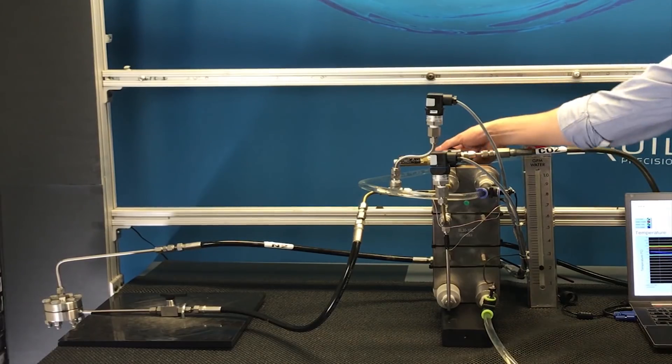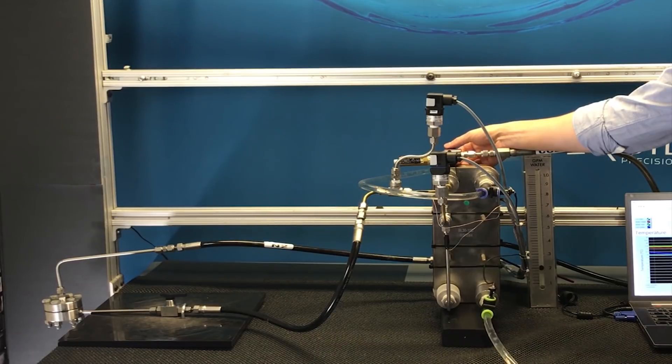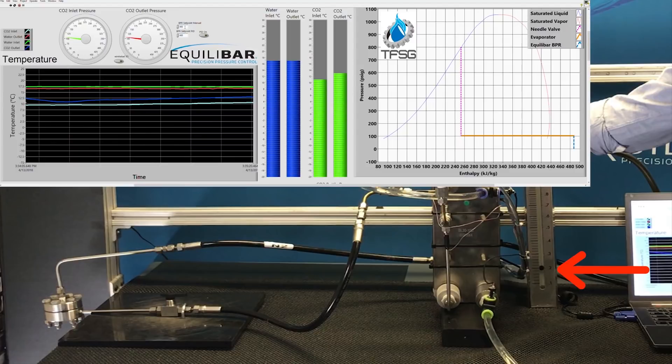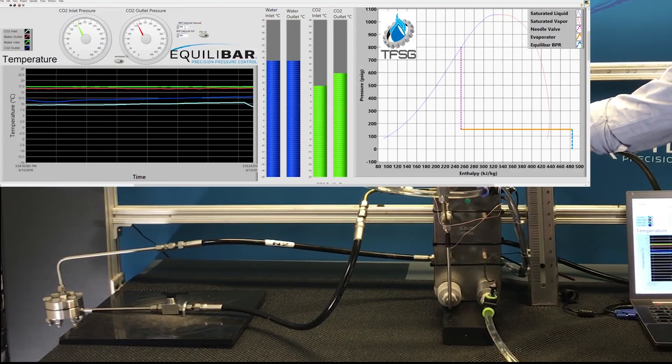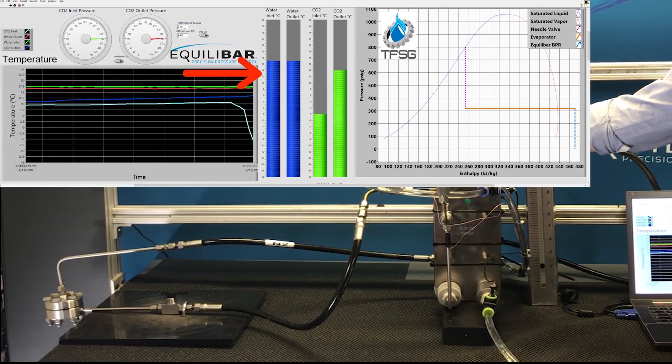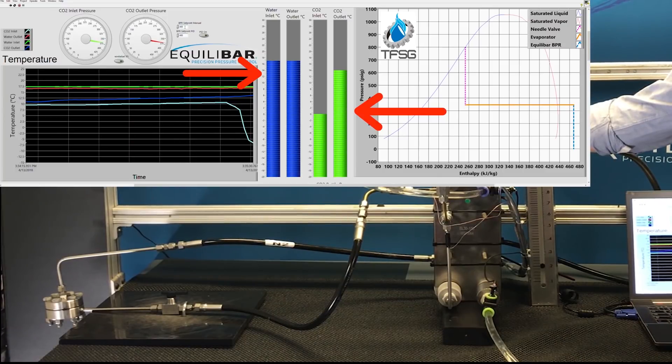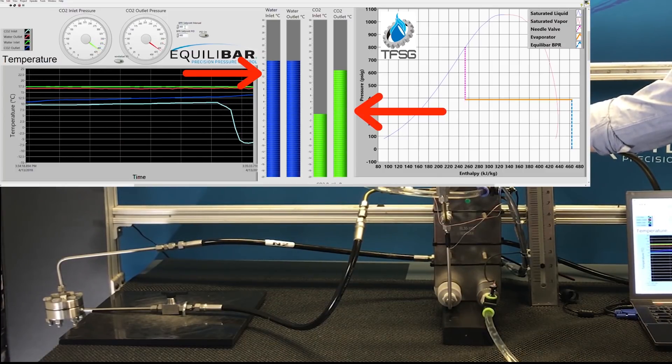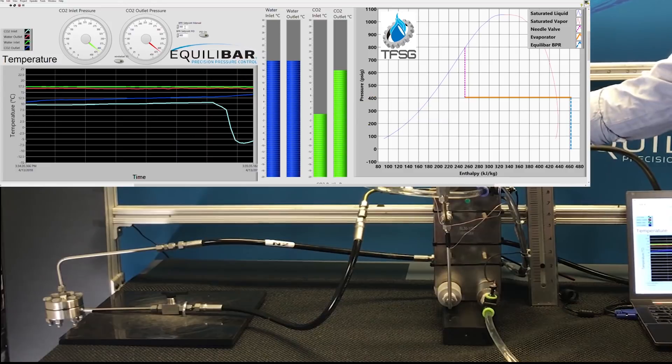As the needle valve is open, CO2 flows into the system and the heat exchange process in the evaporator begins. The heat load in this run is set to 0.2 GPM. The overlay shows two graphics. On the left are temperature plots and bar graphs showing the inlet and outlet temperatures of the water which is our heat load and the CO2 process fluid. Green represents CO2 temperature and blue represents the heat load temperature.